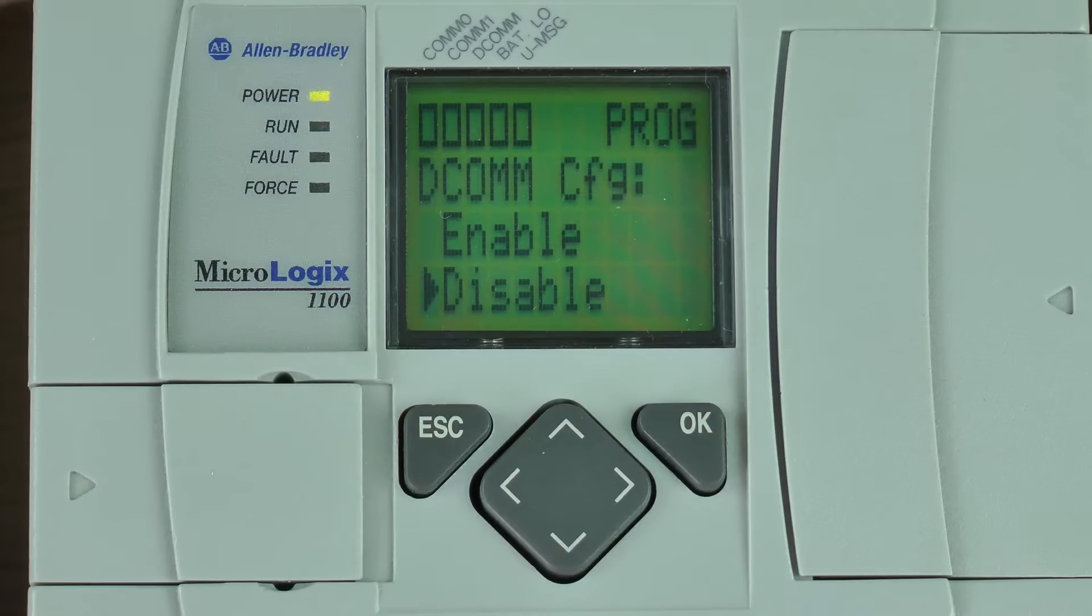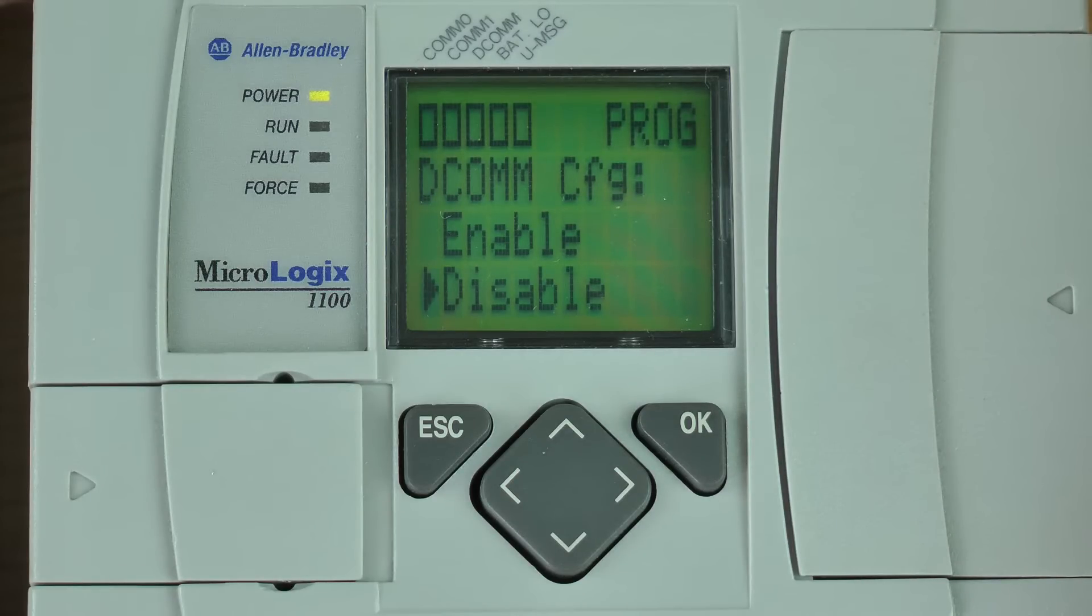Now here you can see DCOM config disable is selected and we can tell that the DCOM config is not on because if we look at the top of the LCD screen, that middle square is hollow and that's the indicator for the DCOM setting.